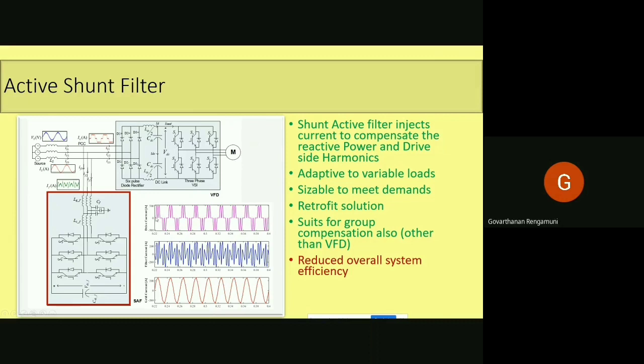You can see the waveform here. The drive current is supposed to be like this, the first waveform. So if you are injecting the filter current like the second waveform, you can reconstruct the grid current into a sinusoidal one. So the drive current will be non-sinusoidal and the grid current will be sinusoidal. The difference of grid current and drive current will be injected by this active filter. This active filter normally senses the polluted current at the drive side, and it will inject the required harmonic currents to reconstruct the waveform into sinusoidal at the grid side. This is what it is doing.